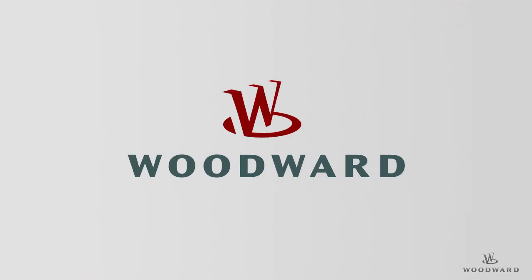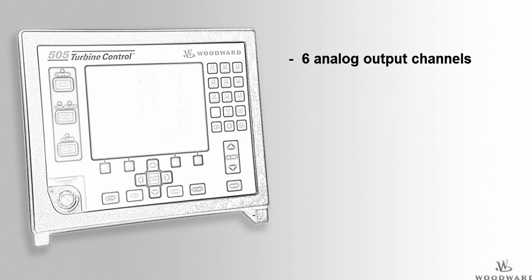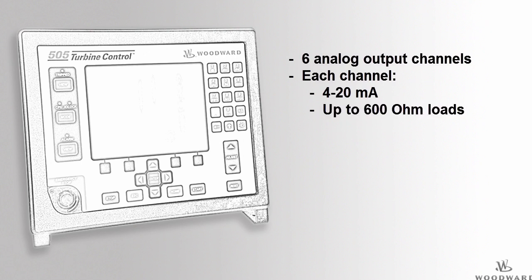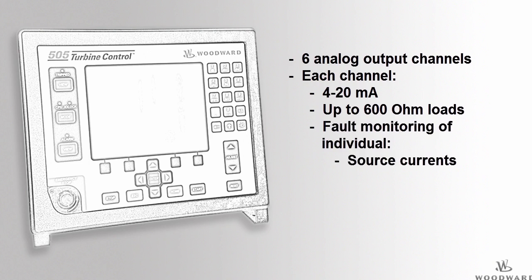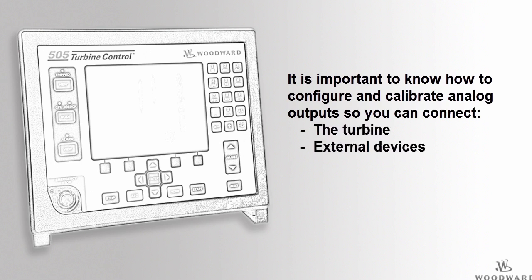Hello and welcome to the 505 tutorial for configuring and calibrating analog outputs. In this tutorial you will learn how to configure and calibrate analog outputs. The 505 has six 4 to 20 milliamp analog output channels. Each channel can drive up to 600 ohm loads and provides fault monitoring of individual source and return currents. It is important to understand how to configure and calibrate analog outputs so you can connect your turbine and external devices to your 505 controller.